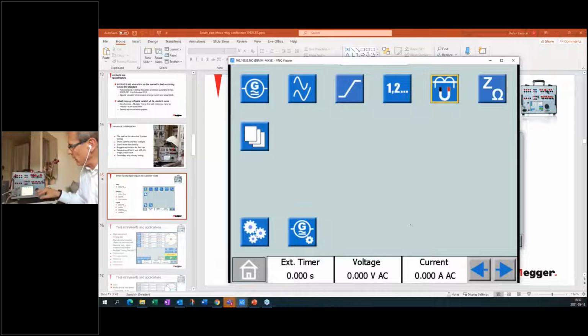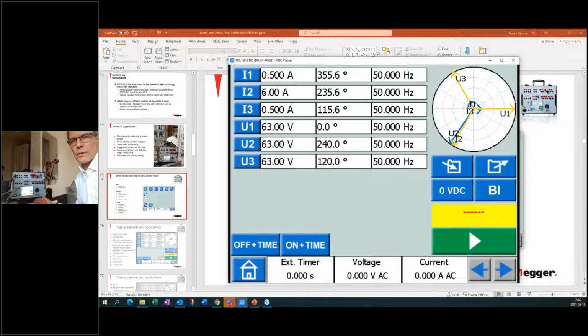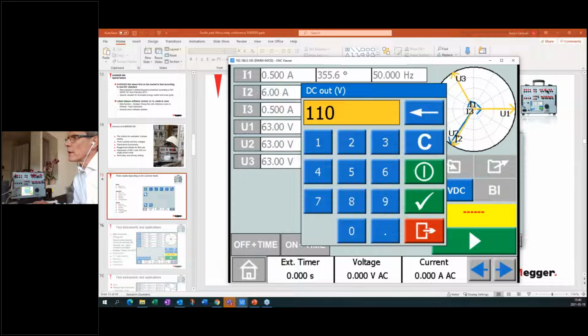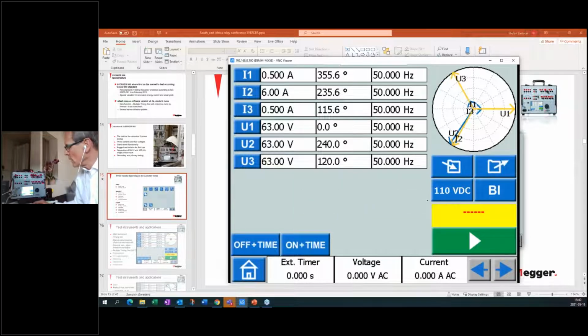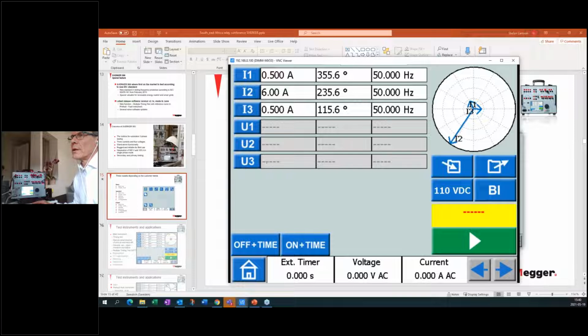So everything is connected. I will go into the main instrument. This is the easiest instrument you can work with to do relay testing. And you can do timing tests, and you can find thresholds. So I just show you very simply. I need to power up the relay here in this case. So I will give 110 volts to the relay like this. Now I can actually see the relay starting up. Also, in this case, I don't need to, I shall just inject current. So I disconnect the voltage, switch off the voltage channels.